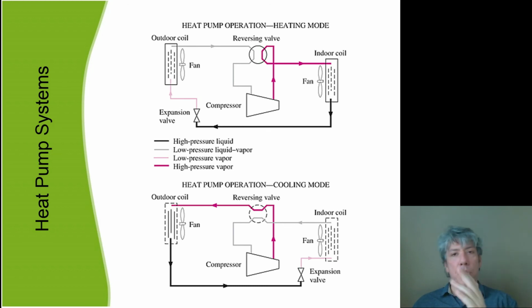We came out of the compressor with a high temperature, high pressure gas, went through the reversing valve to the indoor coil, and the indoor coil only allows high temperature, high pressure liquid to leave and go along that black line to the expansion valve in the upper figure. The expansion valve does exactly as it did before. Some of the refrigerant boils off, goes into the vapor phase, but the pressure and temperature of the refrigerant drop significantly. So now, even though the outdoor temperature may be 30 degrees, if the refrigerant is at 20 degrees, it's going to pick up heat from the outdoors.